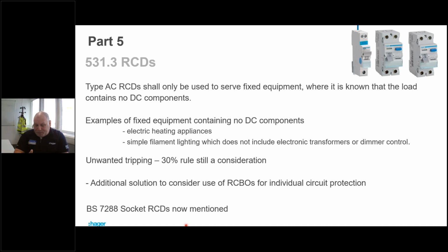We could possibly make sure that the wiring was of such a nature that we didn't need to protect the wiring with an RCD. But we could put the socket outlets onto these new socket RCDs. So each individual station would then have its own socket outlet RCD protection. Computer equipment has a lot of earth leakage, so it might be a way of getting rid of that nuisance tripping on large areas.